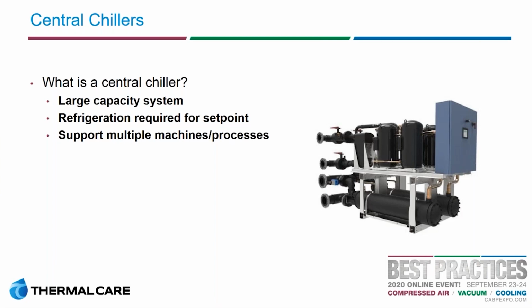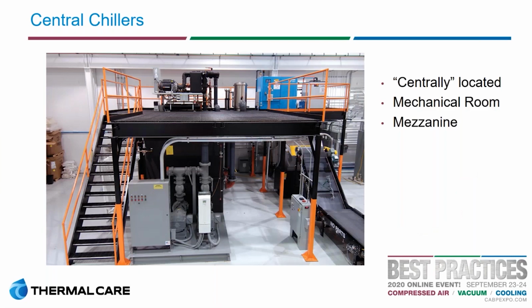A central chiller is in contrast to what would be known as a portable chiller. Those are small packaged units that are typically located near the usage point, where a central chiller is a large capacity unit that's generally located in, say, a mechanical room or on a mezzanine, and it supports an entire facility or a wing of a facility, many machines, and it has stages of unloading. It utilizes a tank and pump system that would complement it to distribute the water throughout the plant. And so what we have here is a good example of a central chiller setup.